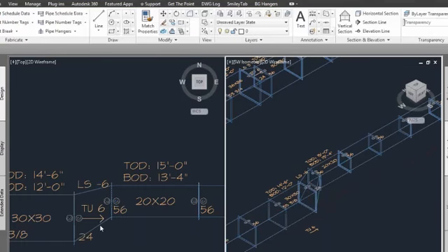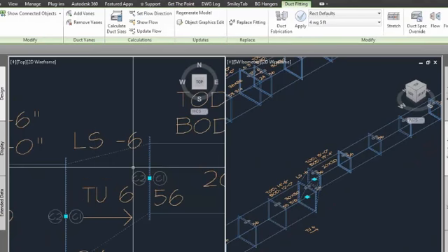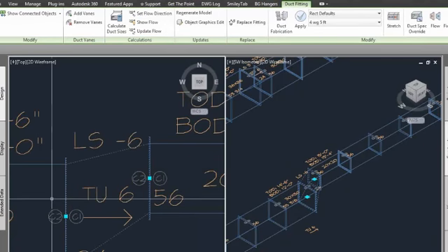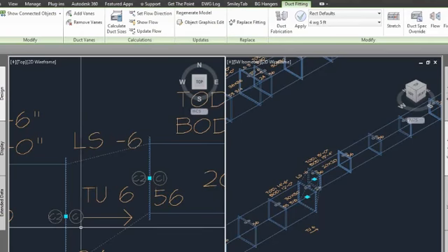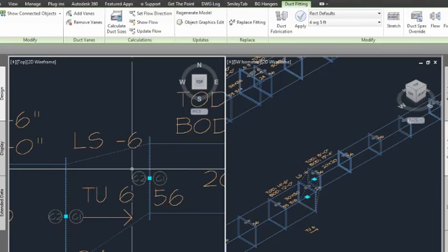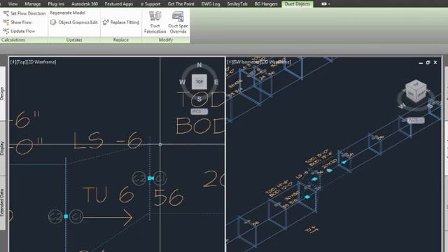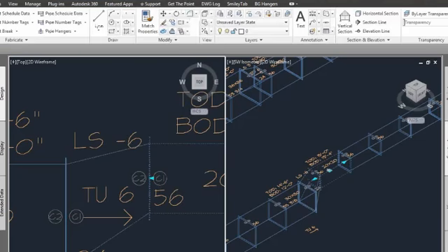Now one thing to notice with our version 6.1 software is that it put this transition in the correct orientation. It matched this connector 1 up with this connector 2, and over here this connector 2 with this connector 1. So for direction of flow, it should always be connector 1 to connector 2. Prior to our version 6.1 software, it did not work this way. Whatever connector you selected first, that's where it put connector 1 of the transition. That could cause some problems, especially with your tagging, because your transition would be rotated upside down, which could cause some of your tags to report incorrectly. With 6.1, we've drastically reduced, almost to zero, the number of times that's going to happen.